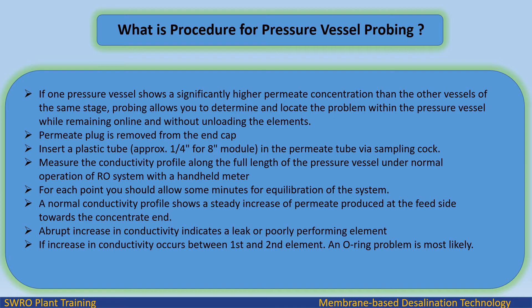If an increase in conductivity occurs between the first and second element, an O-ring problem is most likely the cause.